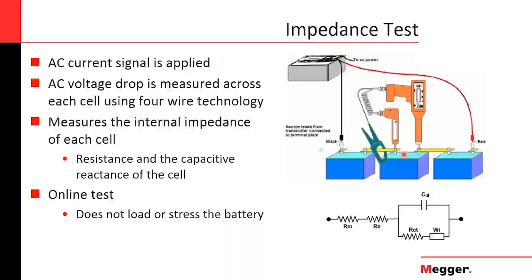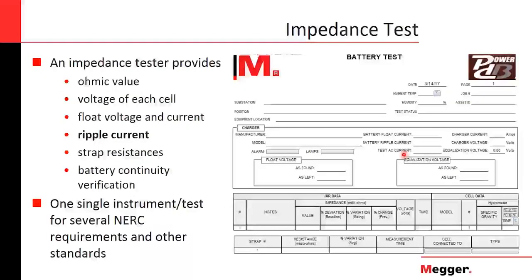And another big advantage of this test is that it is an online test. You don't need to remove the battery out of service to be able to perform the test. You just need to be sure it is fully charged. And this test doesn't load or stress the battery. You're not affecting the battery by any means with this test. So it's totally innocuous. It won't do anything to your battery, and will give you very good information to determine the health condition of the battery.